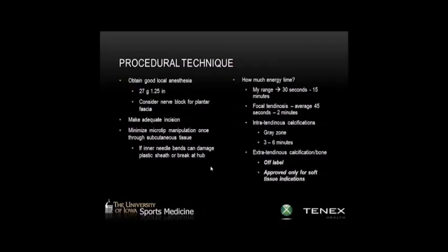What we don't want is bending of the needle where it's connecting or pushing up against the sheath, because the needle is vibrating very fast, and that can cause damage to the sheath and can even put stress through the needle and cause damage there as well. So we want to really avoid how much maneuvering you're doing in the tissue.